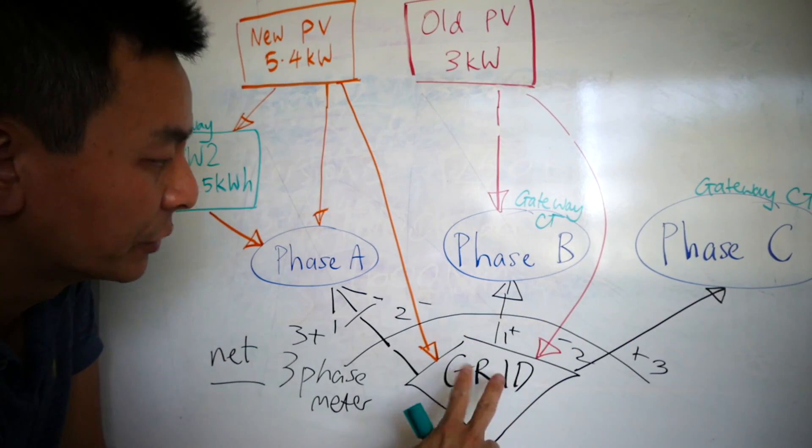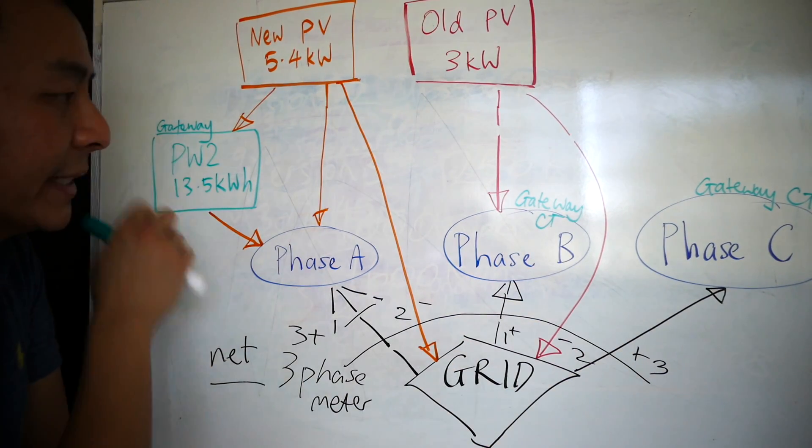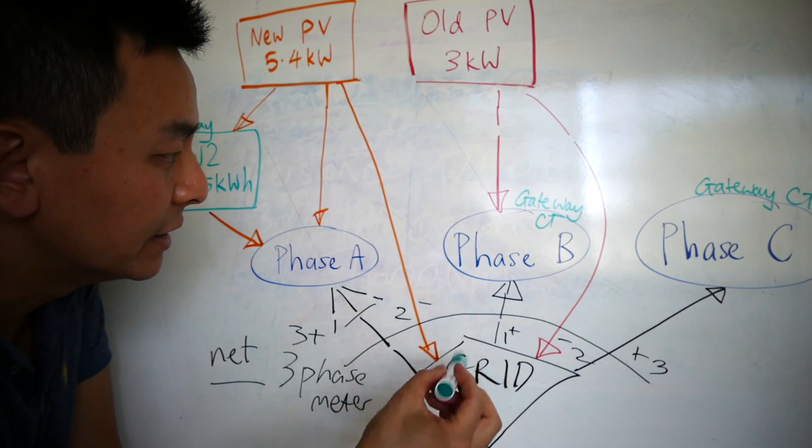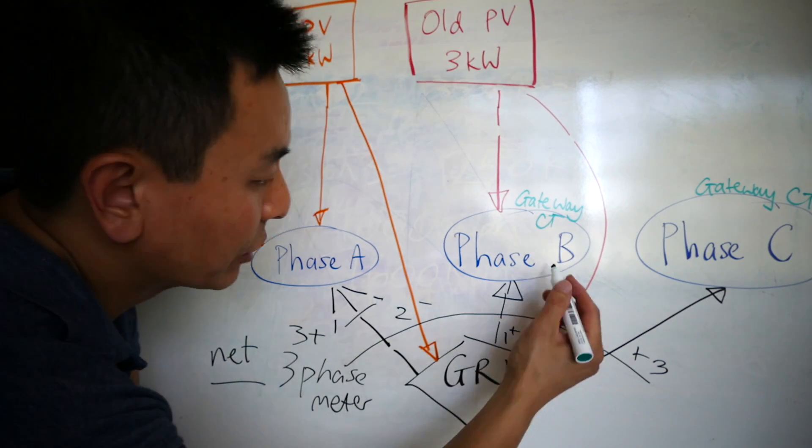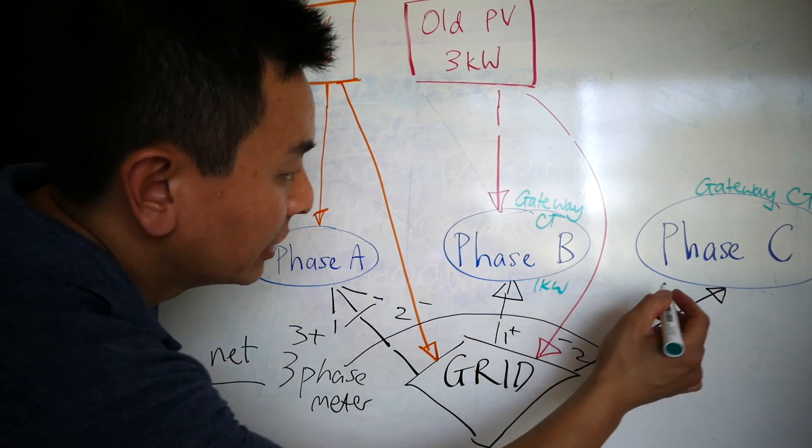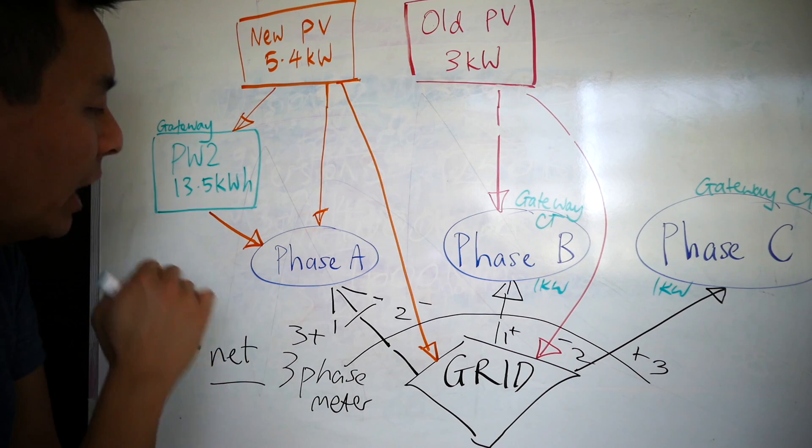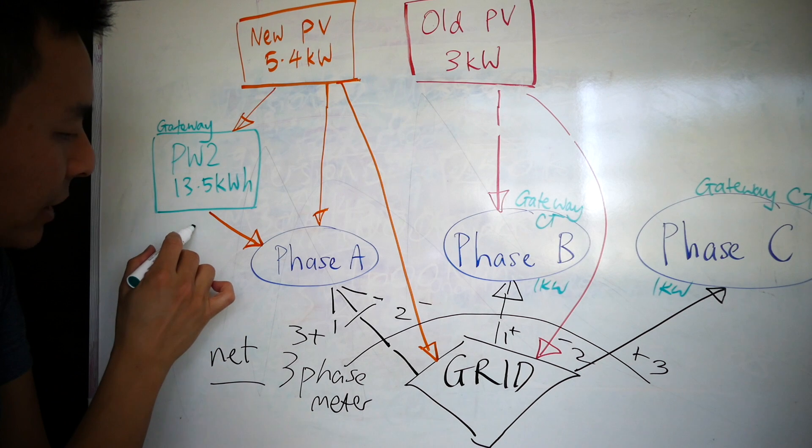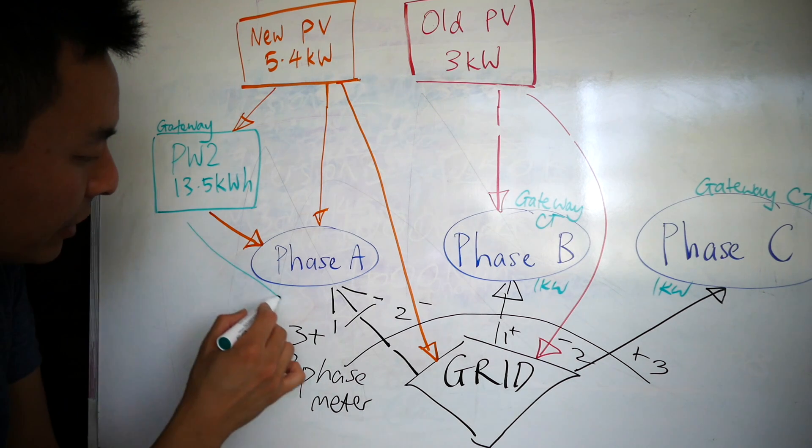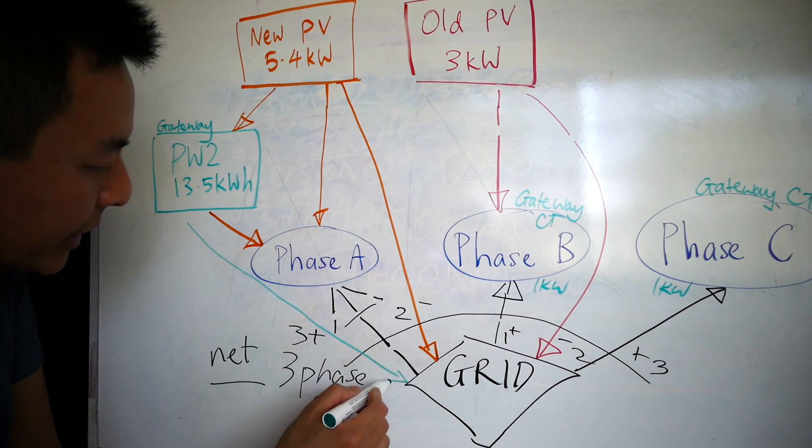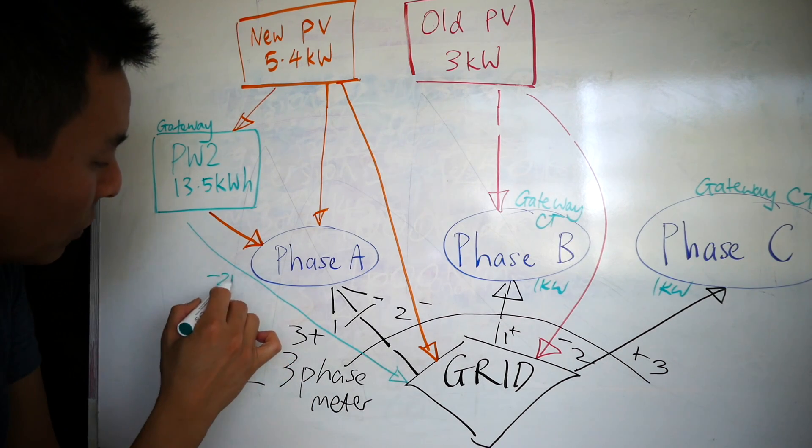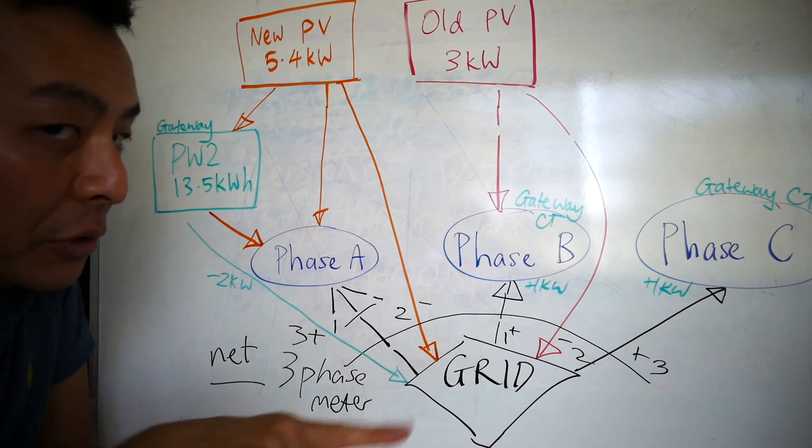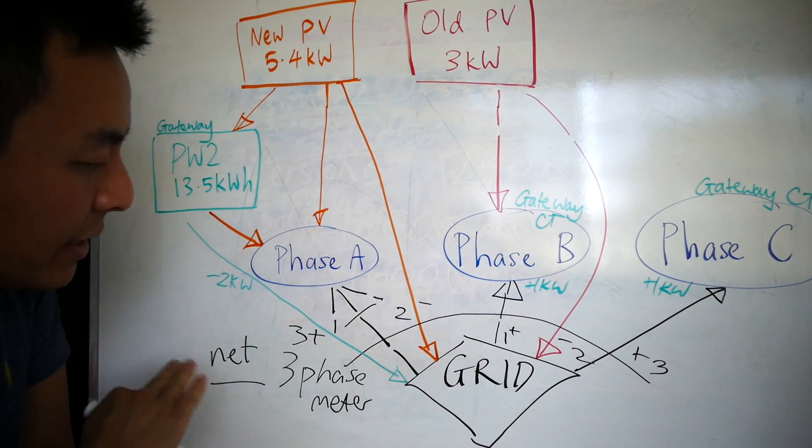These two phases at night use the grid energy, but with the gateway there's something called a CT clamp, which basically is like a little meter for the gateway. Anything that the B phase and the C phase uses from the grid, let's say for example it uses 1 kilowatt and this one uses 1 kilowatt, the Powerwall 2 will sense that using the gateway and discharge 2 kilowatts back to the grid.